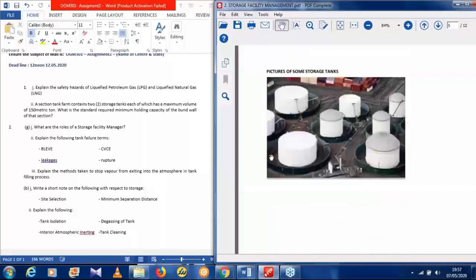These bond walls are designed in such a way that they must be able to occupy 110% of the capacity of that tank. So if this tank capacity is 1 million metric ton or 100 metric ton, the bund wall should be able to occupy 110% of it. Why?